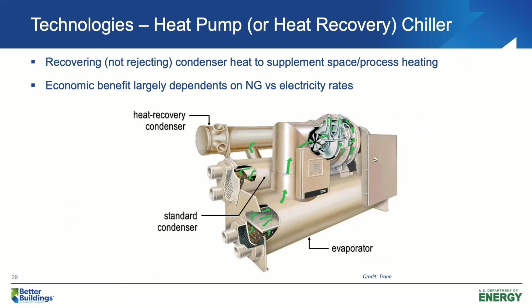The second technology is heat pump chillers. Sometimes they are also called heat recovery chillers. For conventional chillers, we simply reject the heat through cooling towers. But for heat pump chillers, we recover that heat to preheat our heating water or to supplement our boilers. But the drawback is that the cooling energy efficiency of heat pump chillers isn't as high as conventional chillers. So the economic benefit of this technology depends on the natural gas price, electricity price, and the project cost.